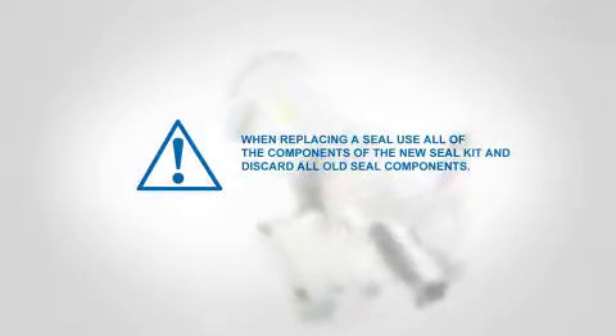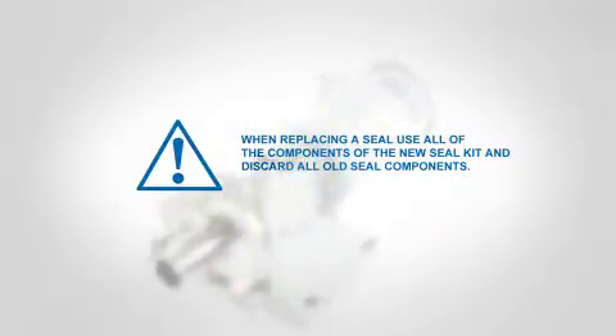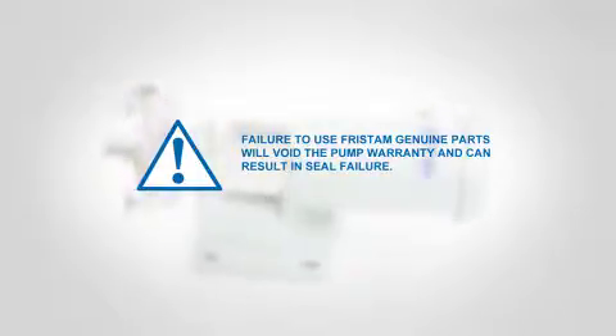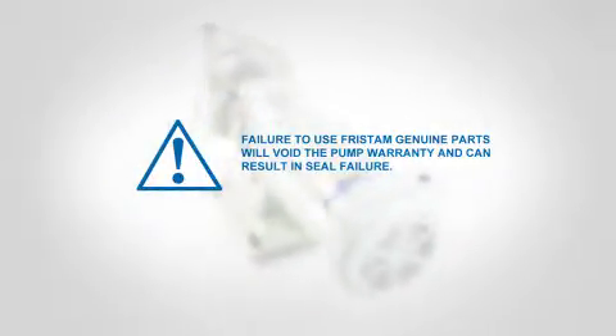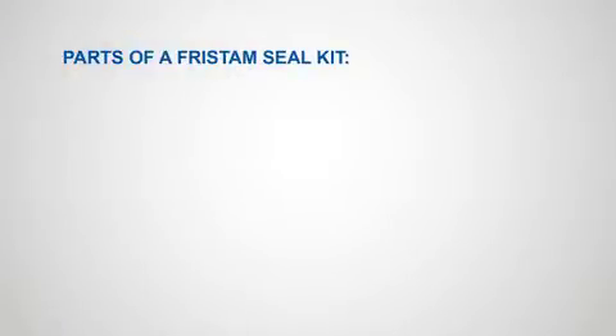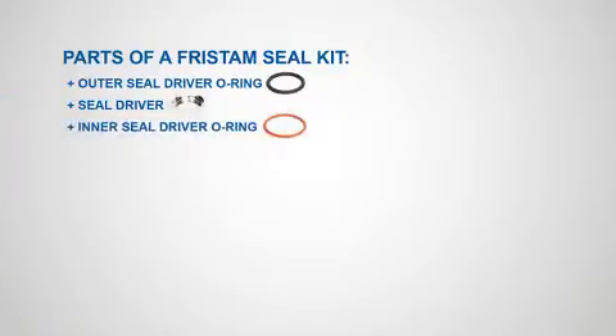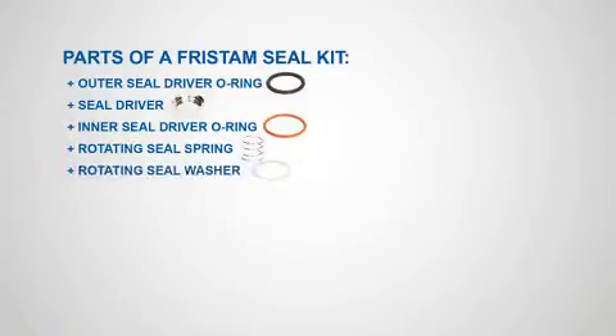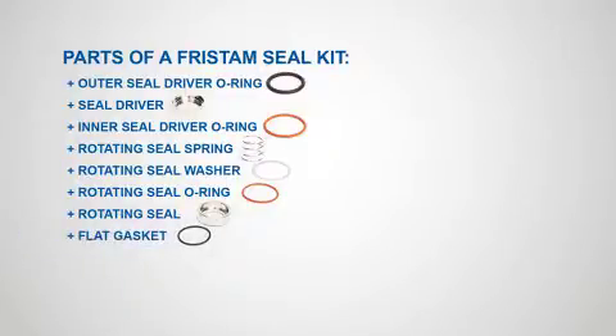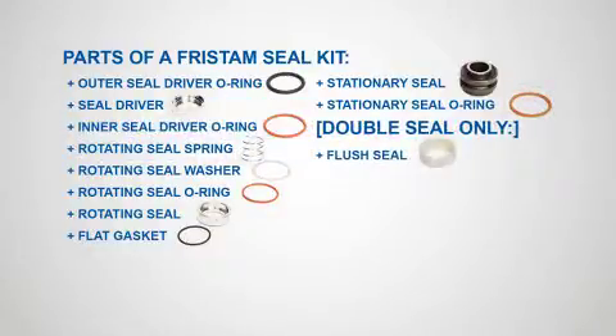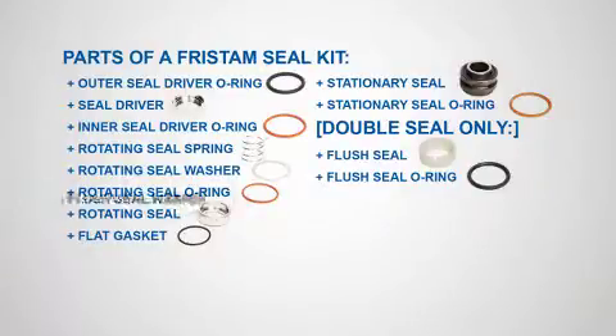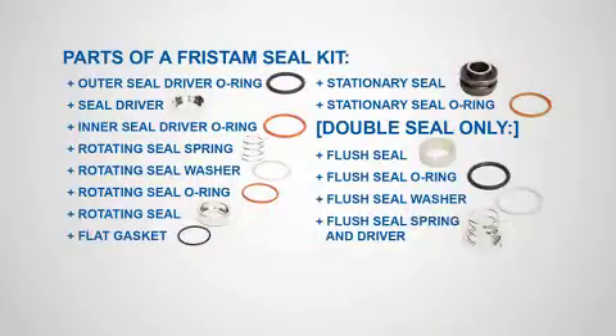Installing the new seal. When replacing a seal, use all of the components of the new seal kit and discard all old seal components. Failure to use Fristam genuine parts will void the pump warranty and can result in seal failure. Parts of a Fristam seal kit: outer seal driver O-ring, seal driver, inner seal driver O-ring, rotating seal spring, rotating seal washer, rotating seal O-ring, rotating seal, flat gasket, stationary seal, stationary seal O-ring, flush seal O-ring, flush seal washer, flush seal spring and driver.